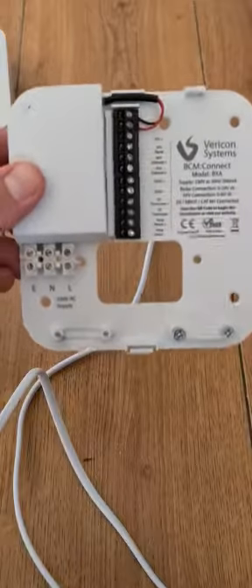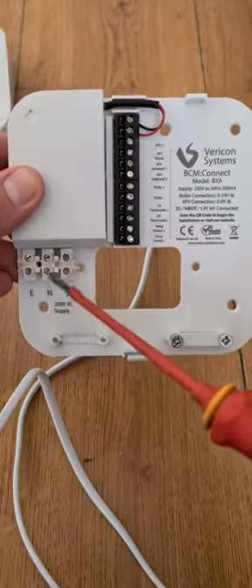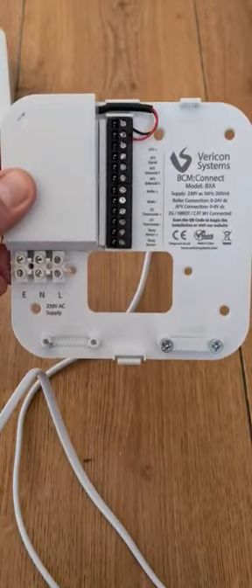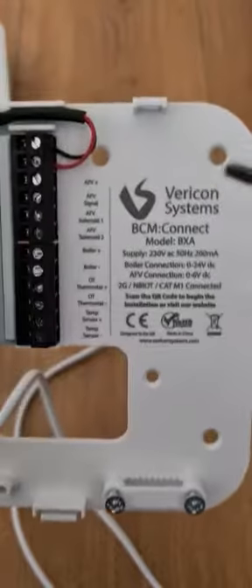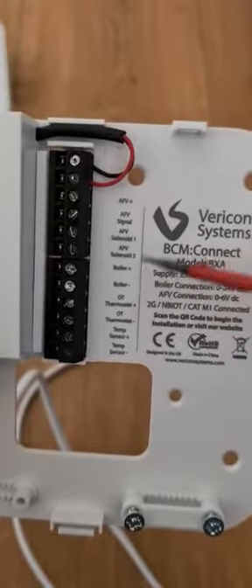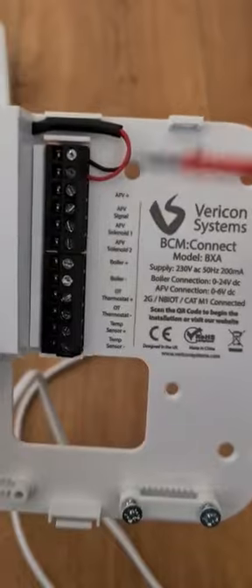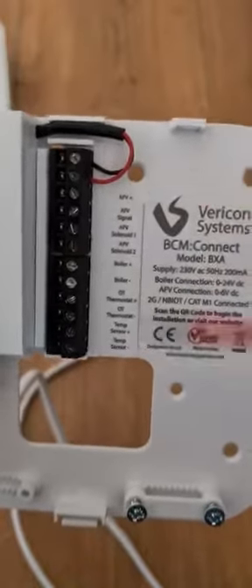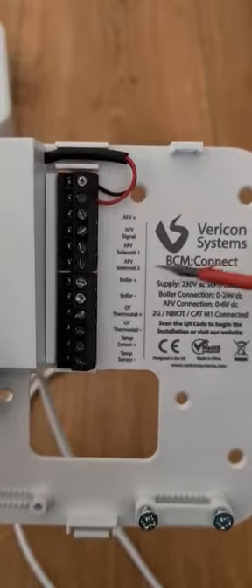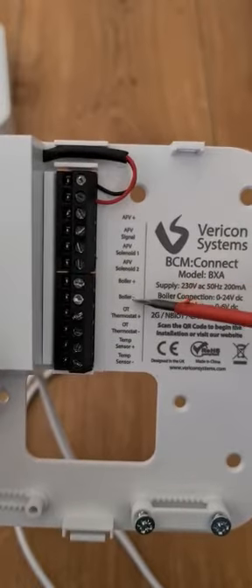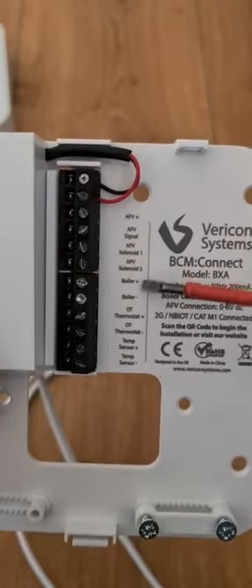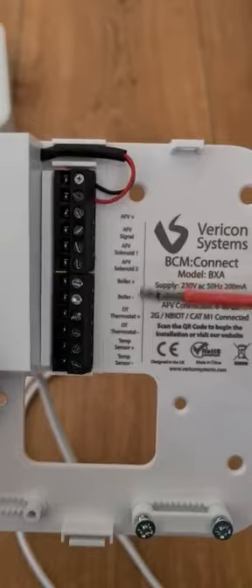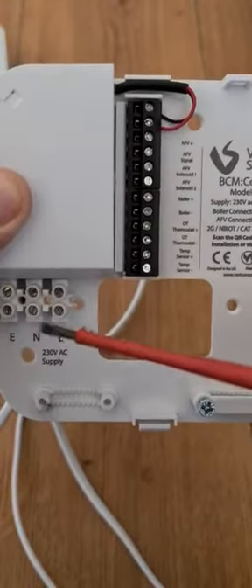On the BCM device, you've got clearly marked the live and neutral, which you can feed your power cables into. Then we're going to use boiler plus and minus. There are quite a few other slots on this device because it has multiple uses, but for the purpose of this trial, we're only going to use the boiler plus and boiler minus. That part is polarity free, so it doesn't matter which way you get those cables round. But you've got to make sure that the power cable goes into live and neutral.